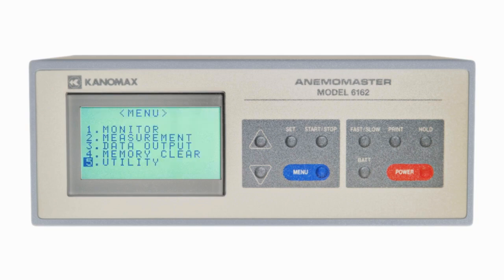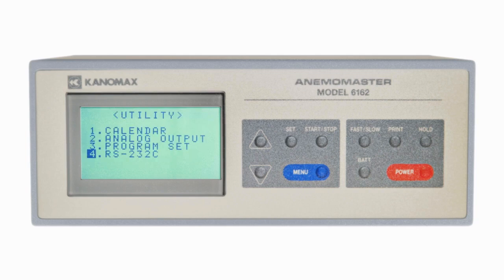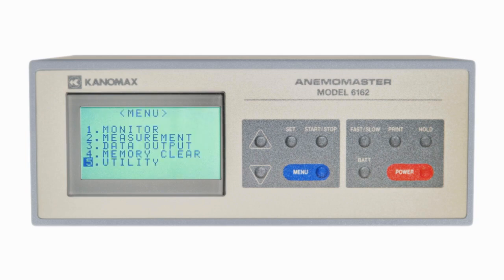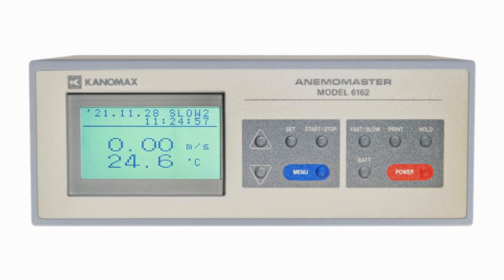For digital output, you have the option to adjust the baud rate of the connection. After selecting the baud rate, you'll be returned to the menu screen to decide whether you want to transfer raw data via monitor or transfer stored data via data output. When transferring raw data to the Kanomax data processing software, make sure to display the monitor screen on the anemometer. While transferring data, don't use other functions.